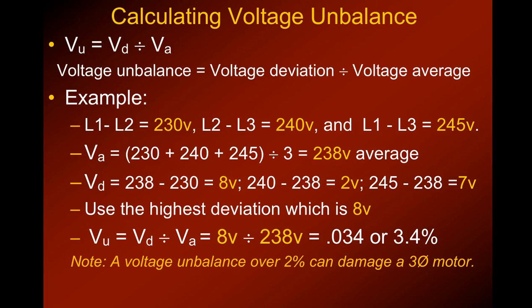The instance I talked about earlier where there was a huge voltage unbalance happened to be that somebody went in and rewired the circuit at the circuit breaker and stole a leg of power. What you'll have to do is you'll have to go back to the circuit breaker in the breaker panel and measure L1 to L2, L2 to L3, and L1 to L3 again, and see if you still have the same voltage unbalance. If you do, it's time to call an electrician.